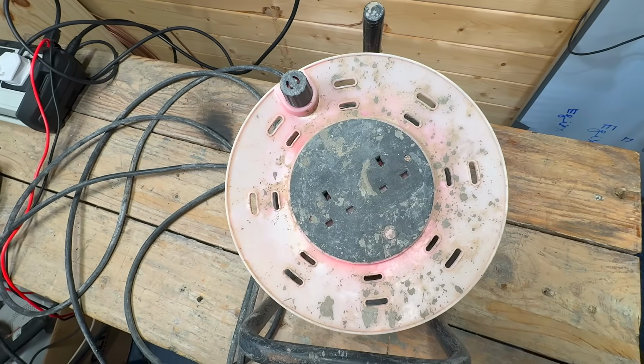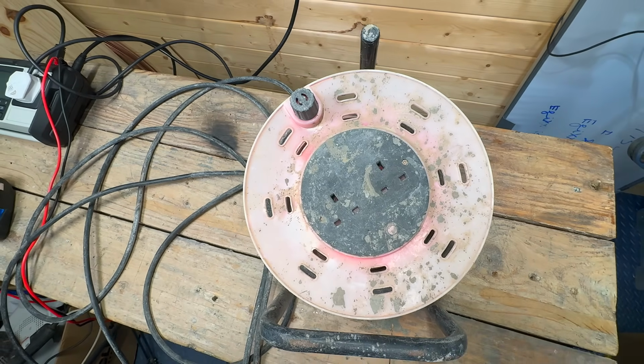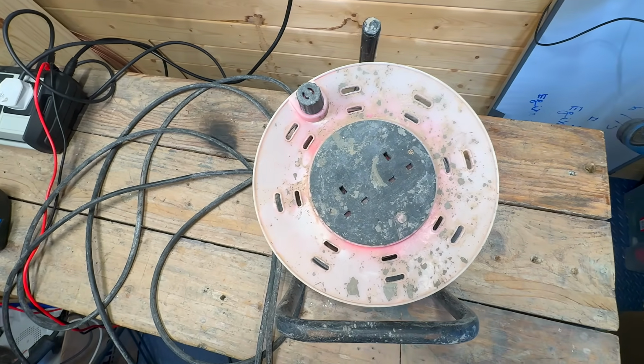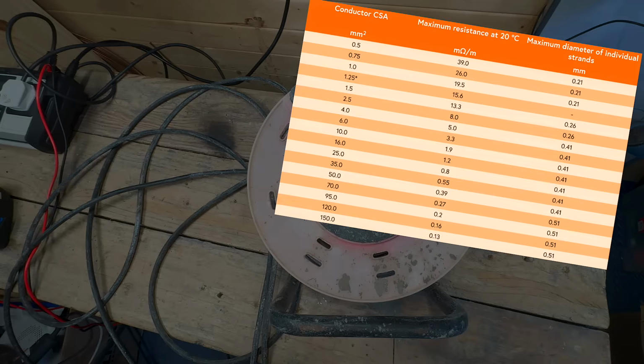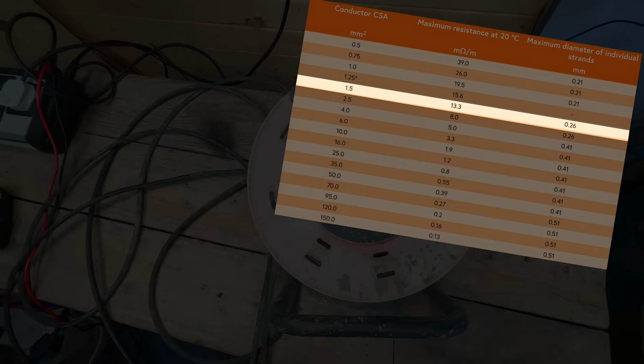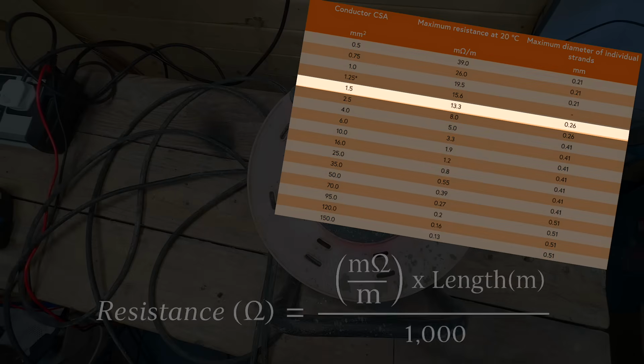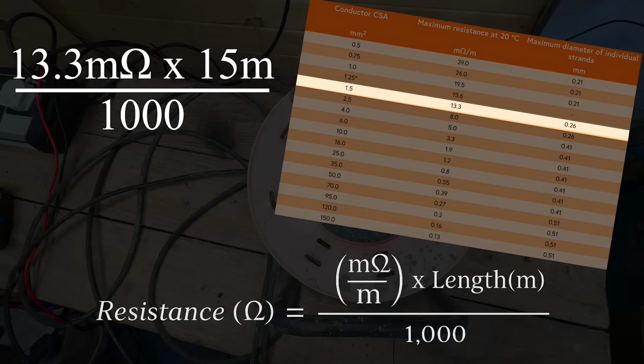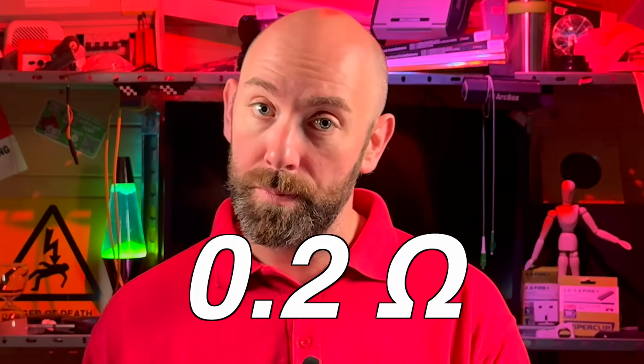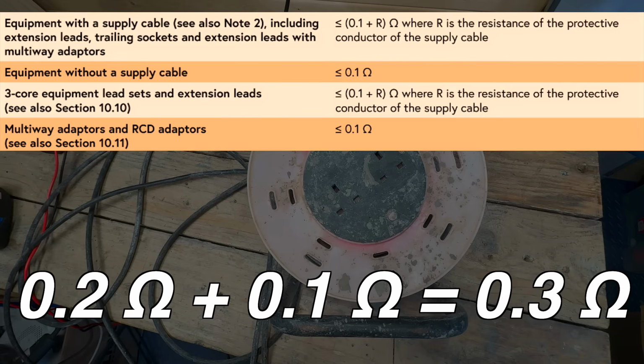So our extension lead is 15 meters long and has a cross-sectional area of 1.5 mm squared. That gives us a resistance, according to table A5.1, of 13.3 milliohms per meter. So by putting this into our formula, 13.3 milliohms multiplied by 15 meters, then divide by 1000 to standardize the unit, we get a resistance of 0.2 ohms. Adding the 0.1 ohms to that gives us a limit of 0.3 ohms. And we can set these limits in the CertSuite app, so we don't need to calculate them every time we test an appliance.